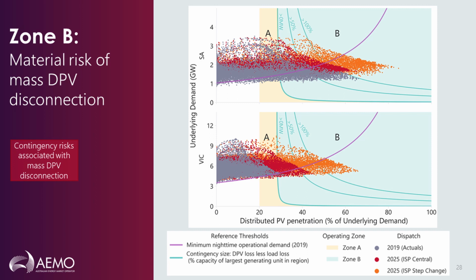Now on to our next zone, which is Zone B, marked in the blue in the charts you can see. From this point, the potential mass disconnection of DPV systems begins to materially impact the effectiveness of contingency management practices. Over the last 18 months or so, we've developed a considerable evidence base demonstrating that a significant portion of DPV generation can disconnect following plausible disturbances in a transmission network.